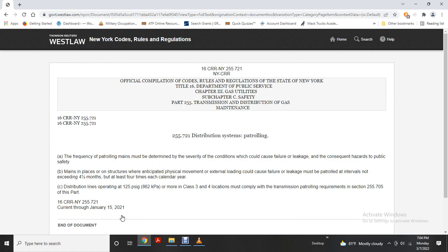Distribution system patrolling. The frequency of patrolling must be determined by the severity of the conditions that could cause failure or leakage, and the consequent hazard to public safety. Mains in places or on structures where anticipated physical movement or external loading could cause failure or leakage must be patrolled at intervals not exceeding 4.5 months, but at least four times each calendar year. A distribution line operating at 125 psi gauge or more in a class 3 or 4 location must comply with the transmission patrolling requirements of section 255.705 of this part.